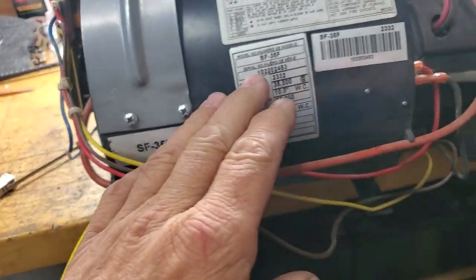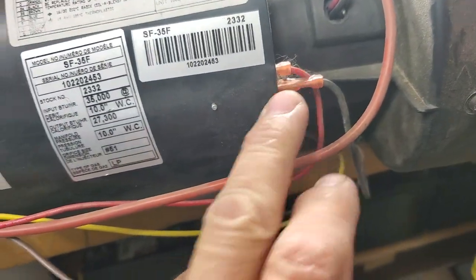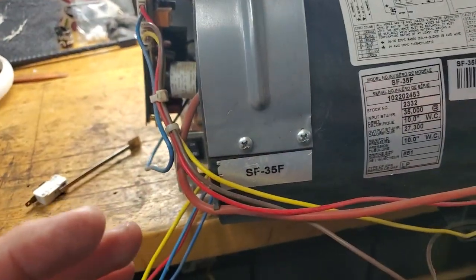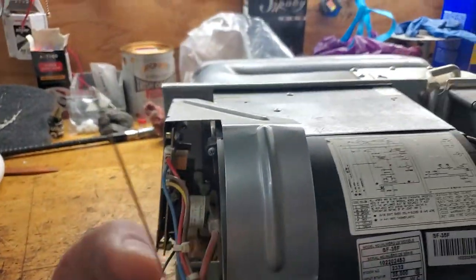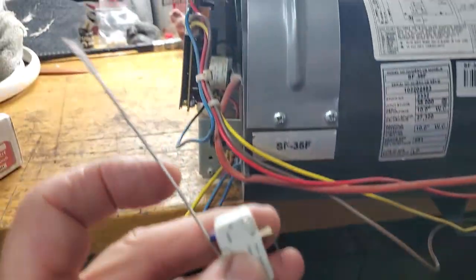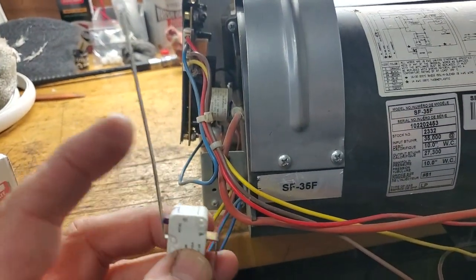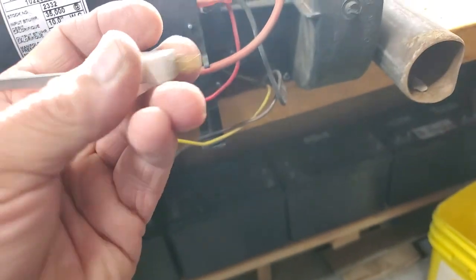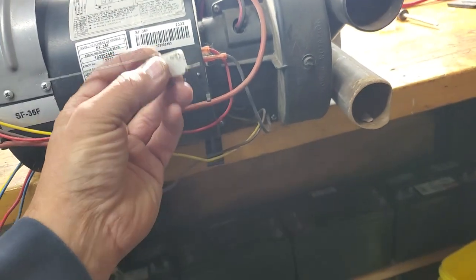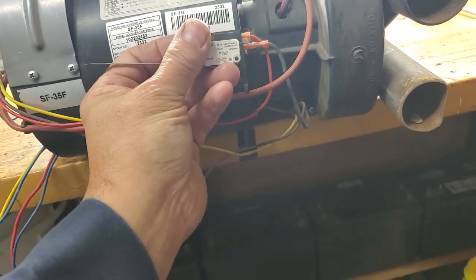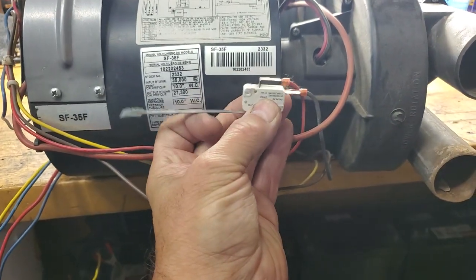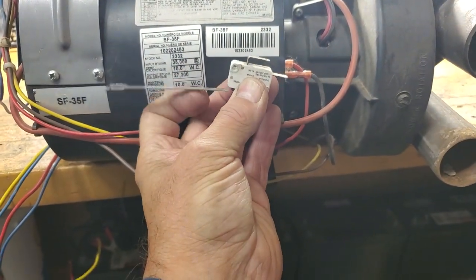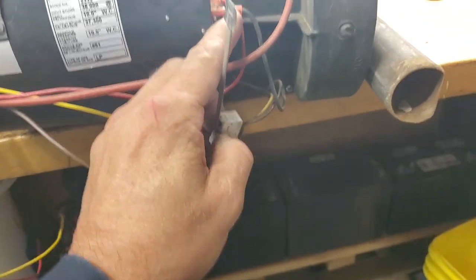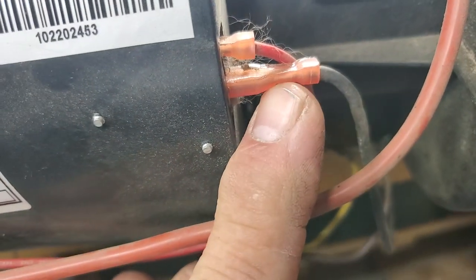The blower comes on. This sail switch doesn't toggle from off to on because the air blew against it. It's got like a little sail on it, or a paddle, I call it. It sits like this, so if this one sits like this, right there, it's got to go up. So this one's hanging upside down. This still might work. I can tell because this female spade connector's out, this one's in, and then there's the bolts, the screws that hold it in.